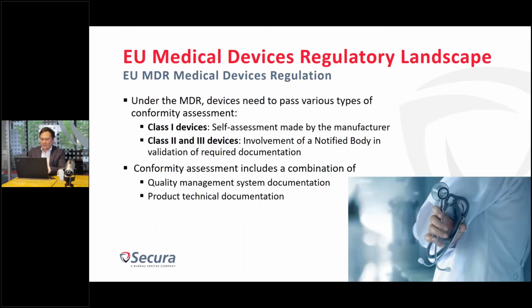So how would the assessment go on in line with the European Medical Device Regulation? For class one devices, so for the ones having the lowest risk of performance and also cybersecurity, in most cases a self-assessment made by the manufacturer is accepted, and the manufacturer is responsible for putting together and maintaining the documentation package in line with the requirements of the MDR. However, for class two and three devices, the involvement of a so-called notified body, a recognized third-party company approved by the medical device regulatory body, is required to analyze the documentation package and also perform necessary testing.